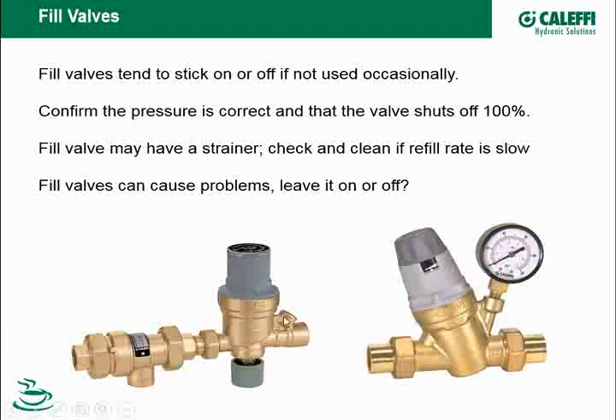So this is a valve that you might find yourself replacing quite a bit. I like to think the Caleffi's got a really good quality one. We do have a valve that you can take apart easily here, and if there is some debris that's stuck in there that's causing it to overfill, you can service it. It also has a strainer around the whole entire body here, so any dirt and debris that's coming from the system, maybe galvanized pipe or something coming into the system here, that dirt and debris can get into your fill valve. So that's one I would probably keep a spare on your truck. Just plan on replacing some of them when you go to use them if they haven't been used for years. Another case where a good quality gauge on it can help you make sure that you're getting the accurate fill pressure in the boiler. And you can see on this is our 3/4 inch fast fill valve. It'll fill about 9 gallons a minute, and it's got a gauge on it also.